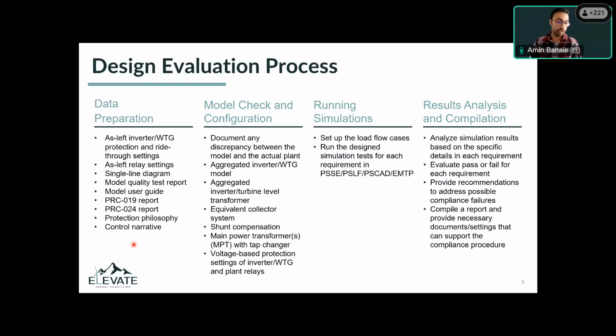Anything else in addition to these can be helpful. I've listed some of them here, like the SLD of the plant, any MQT report, any PRC-24 report, control narrative. This can also help us to understand the ride-through behavior of the plant in a more comprehensive approach. Once we have all this information, we're going to do a check of the model and its configuration to make sure that any setting in that PSSE or PSCAD file matches exactly what's in the field.